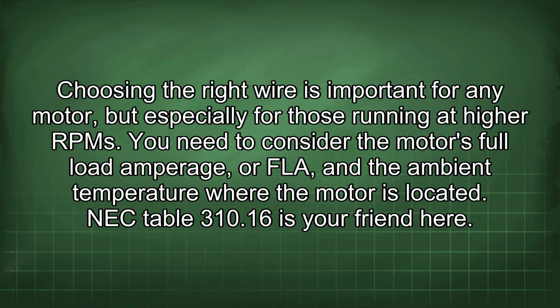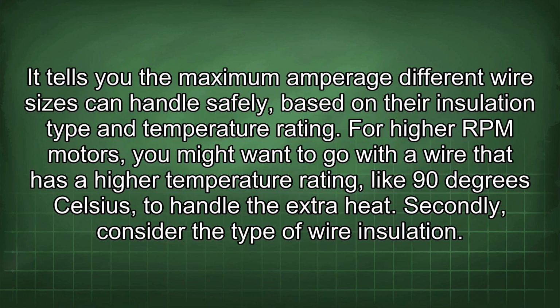Choosing the right wire is important for any motor, but especially for those running at higher RPM. You need to consider the motor's full load amperage, or FLA, and the ambient temperature where the motor is located. NEC Table 310.16 is your friend here. It tells you the maximum amperage different wire sizes can handle safely based on their insulation type and temperature rating. For higher RPM motors, you might want to go with a wire that has a higher temperature rating, like 90 degrees Celsius, to handle the extra heat.